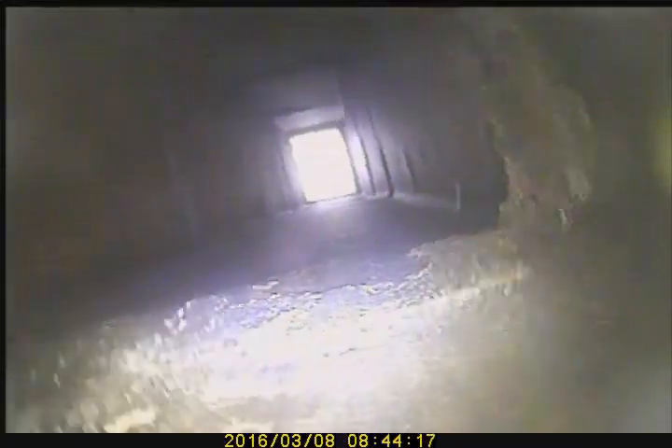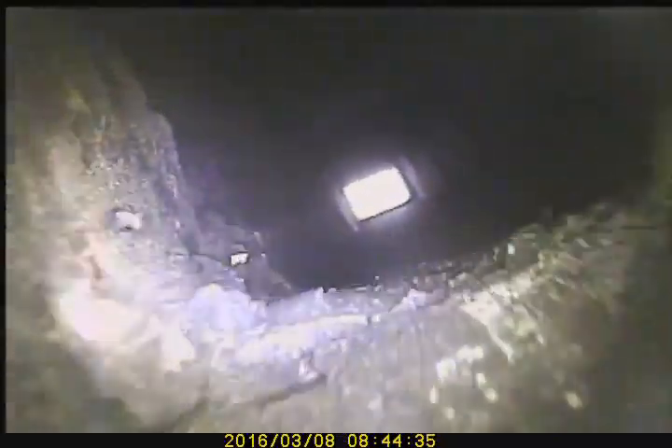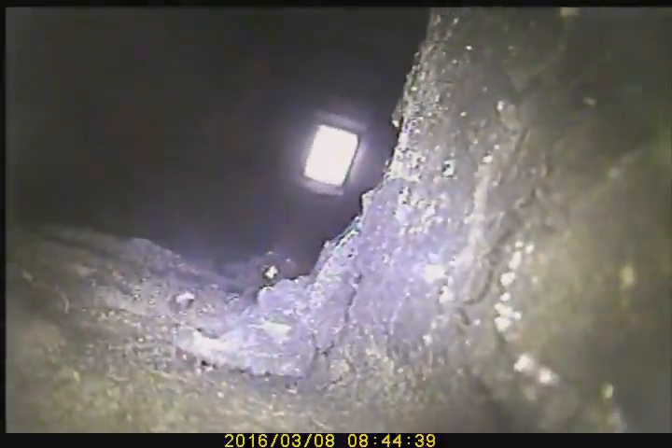There is a lot of cement in this flue. The flue is fairly clean, a bunch of cement. It does look like it transitions — there is a tad more offset here. It almost goes into a possible 13x13. Of course the flue tile is staggered, and it does appear to be a 13x13 at this point.